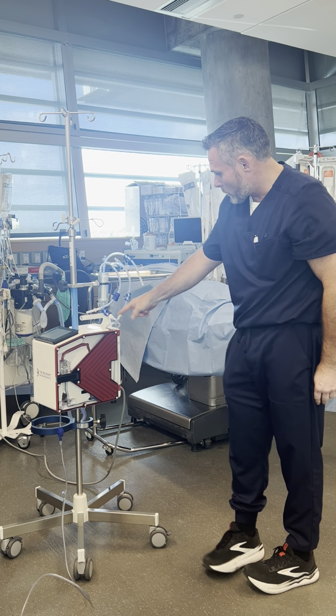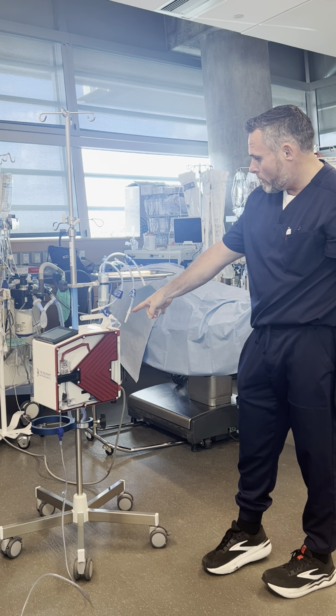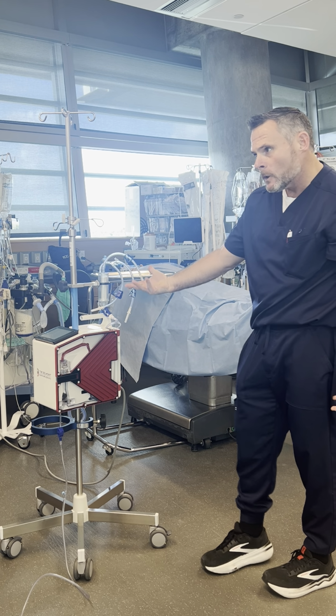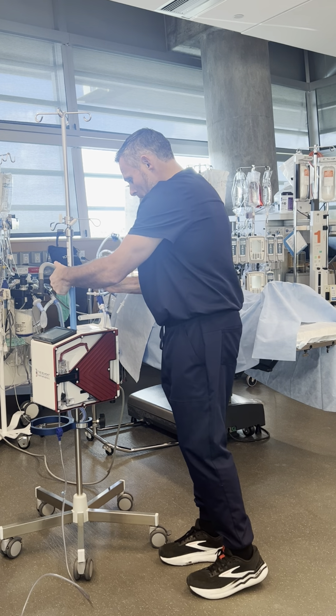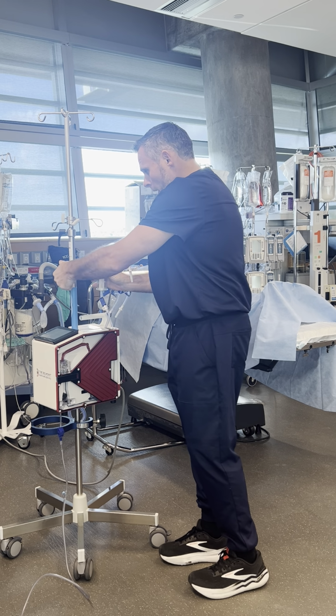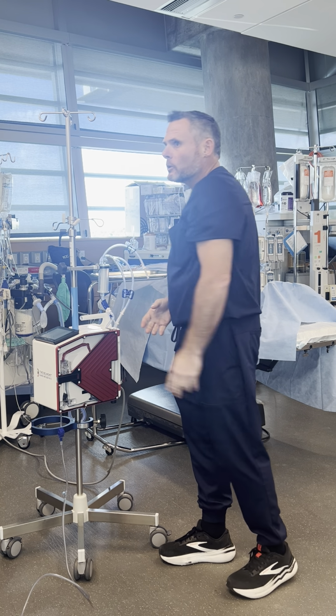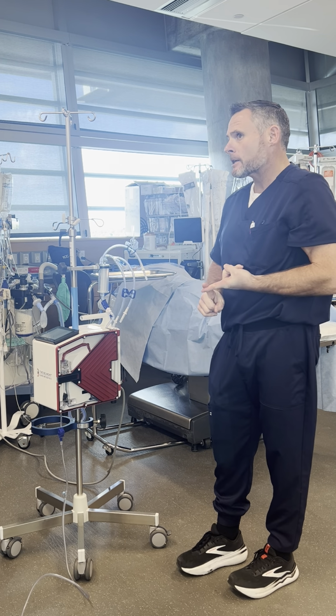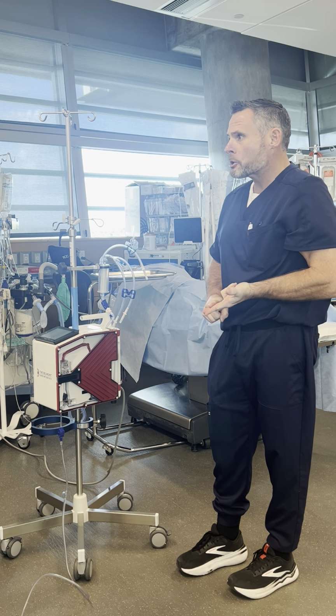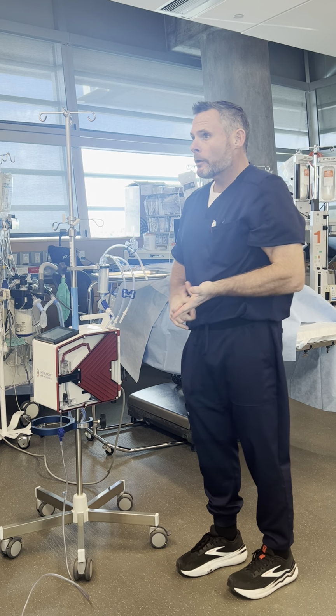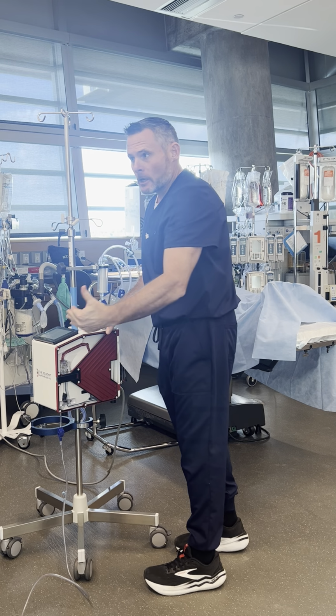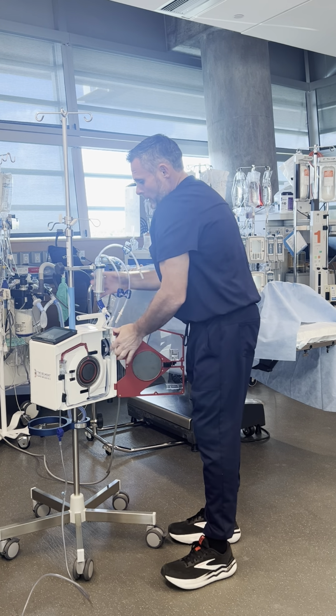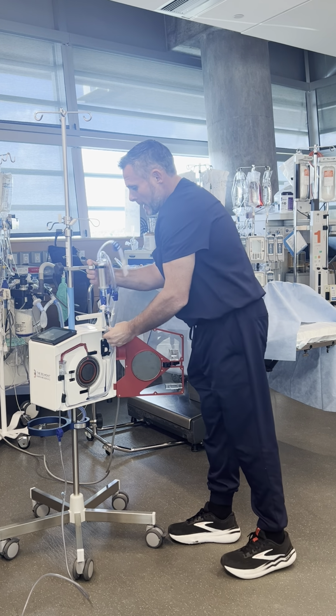And if it looks awkward, well, anybody with a frontal lobe can figure that's not right. So you just fix it. So use common sense right here. And if everything looks fine and you still don't know what the problem is, and it's not air detection squeeze, and it's not high pressure patient line blockage, then just do this. While the machine is on, open up the door, take this out, and put it back in.